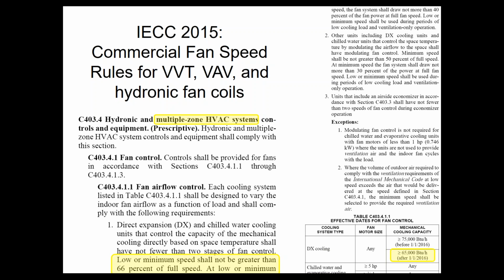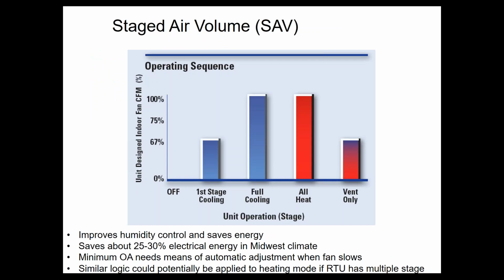We're on this version. So if you have a multi-zone system, like a VVT system or a VAV system, or you happen to have hydronic heating or cooling coils, in those cases, you need to put a 2-speed fan in. Right? We typically call that staged air volume. Typically what happens there is when you're in full cooling, you get 100% of your design CFM. When you're on stage 1, you get 2/3 of your design CFM. Or if you're in vent only mode, meaning no heating and no cooling, you get 2/3.